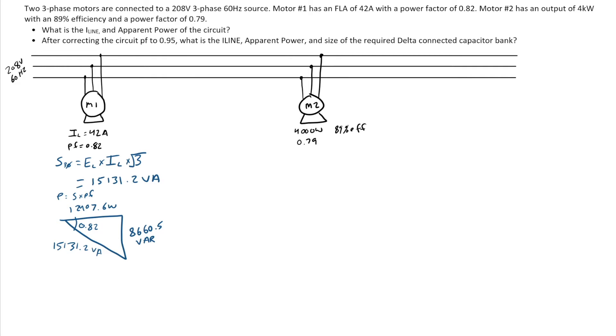Then I'm going to move into motor two. Now this one's a little bit trickier. I'm told it's a 4,000 watt motor. Now when a motor is rated in wattage, that's always talking about its output. So its output is 4,000 watts at an 89% efficiency. But when I'm talking about current going into the motor, I need to turn that into an input.